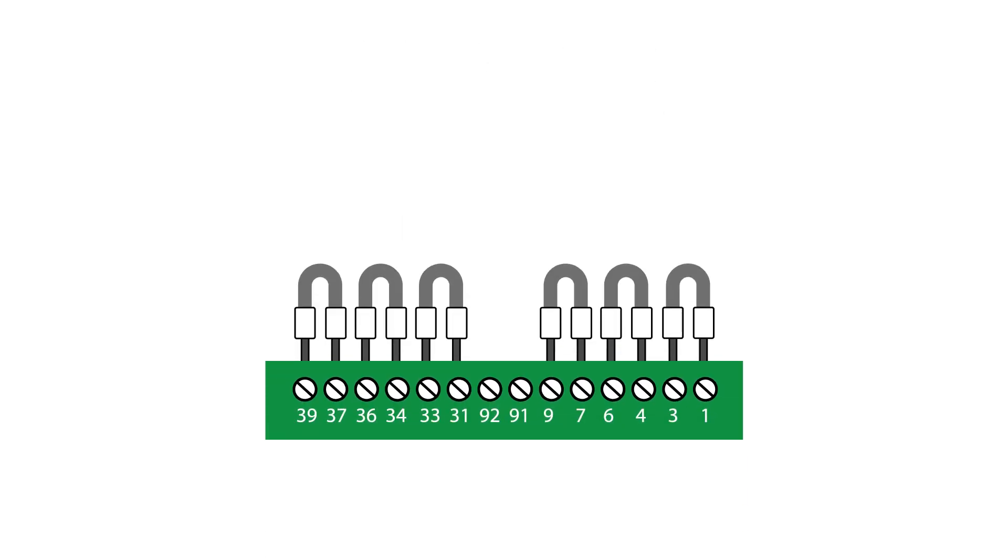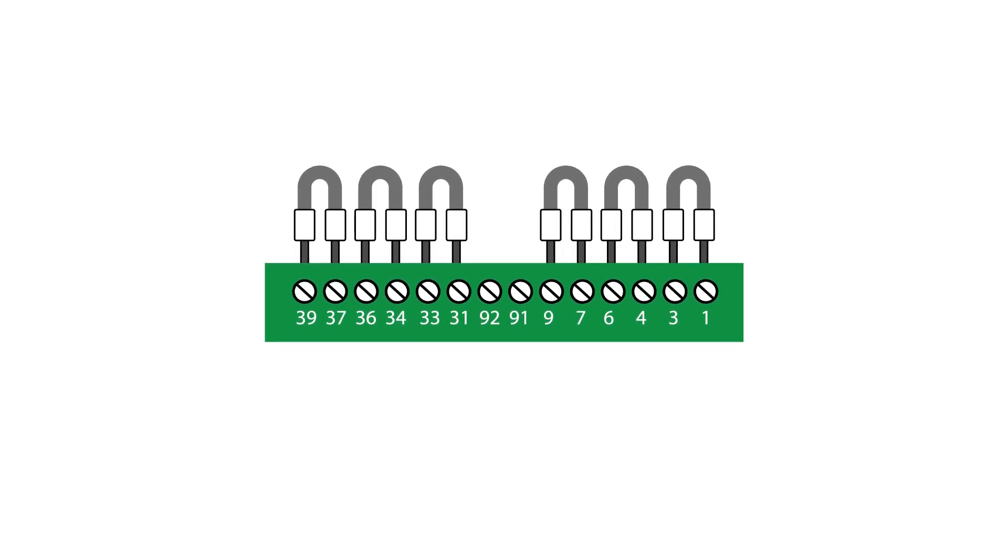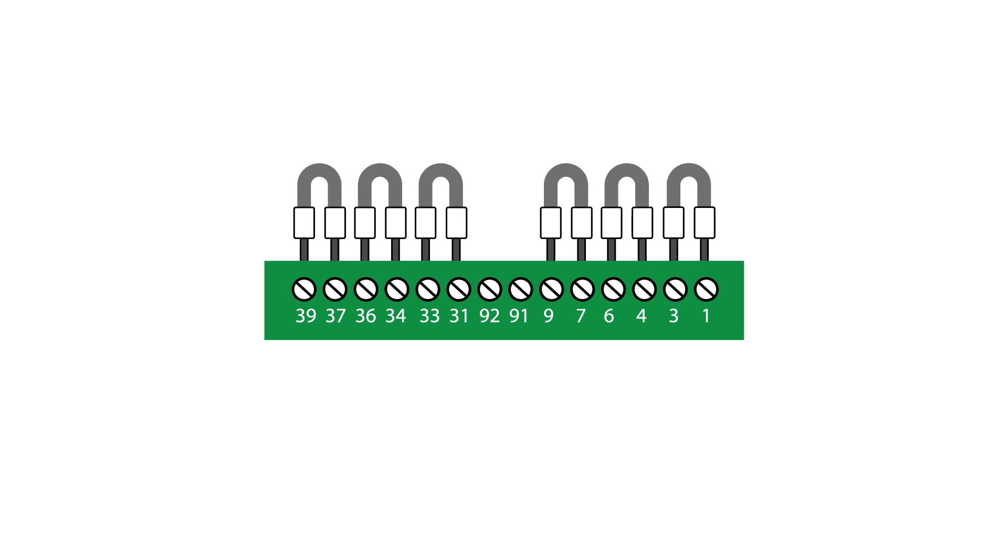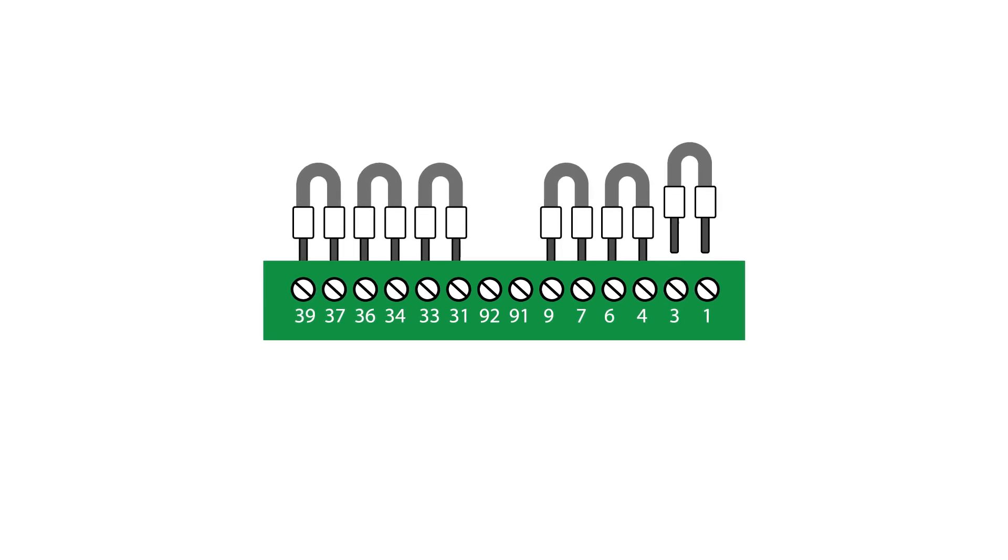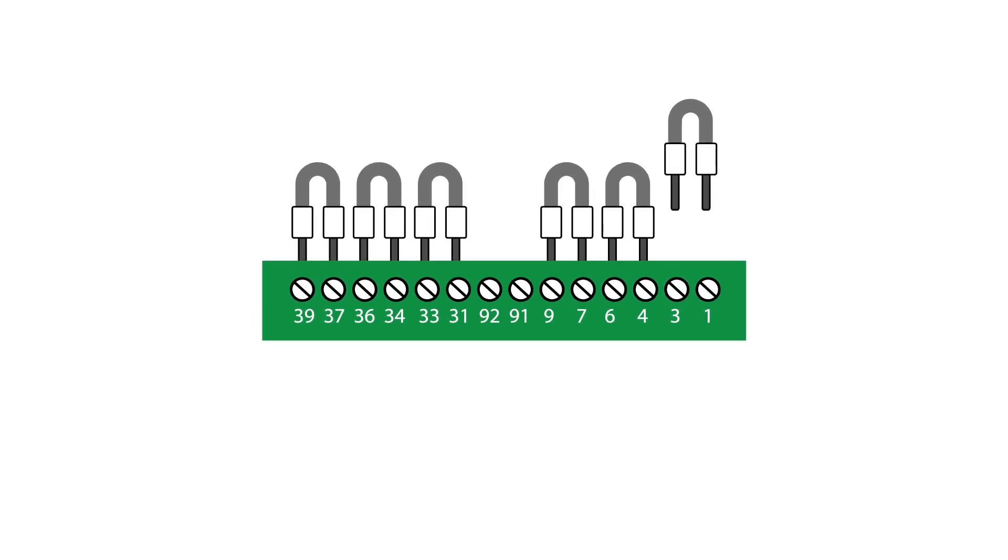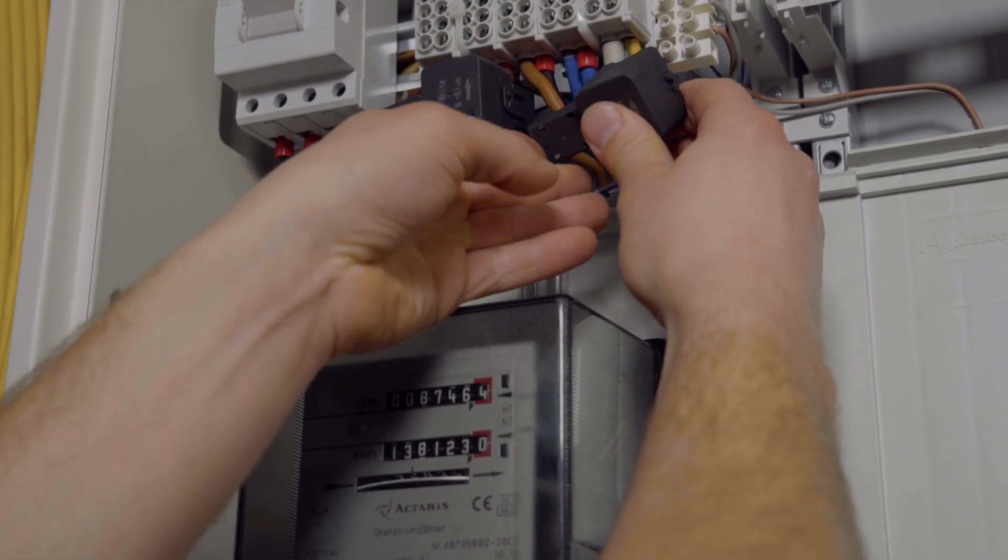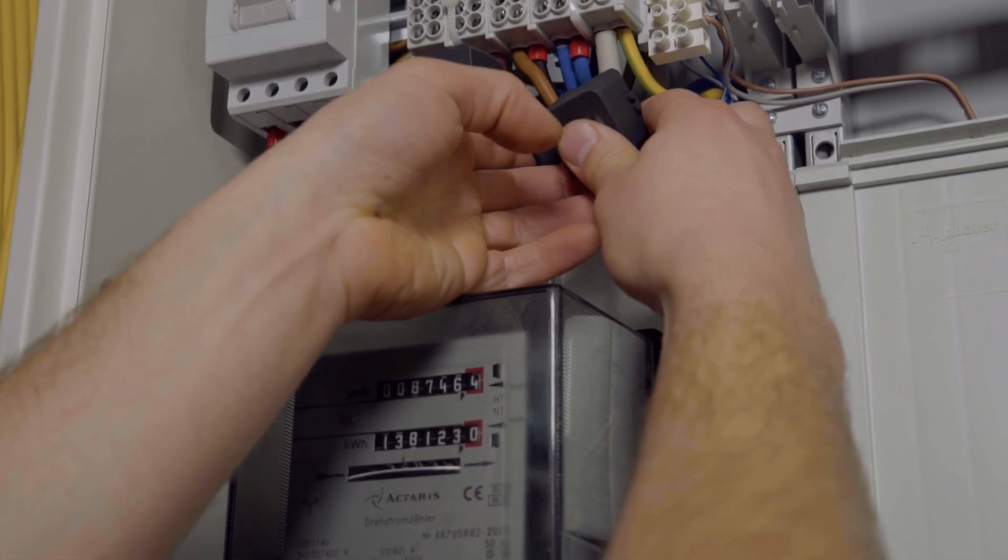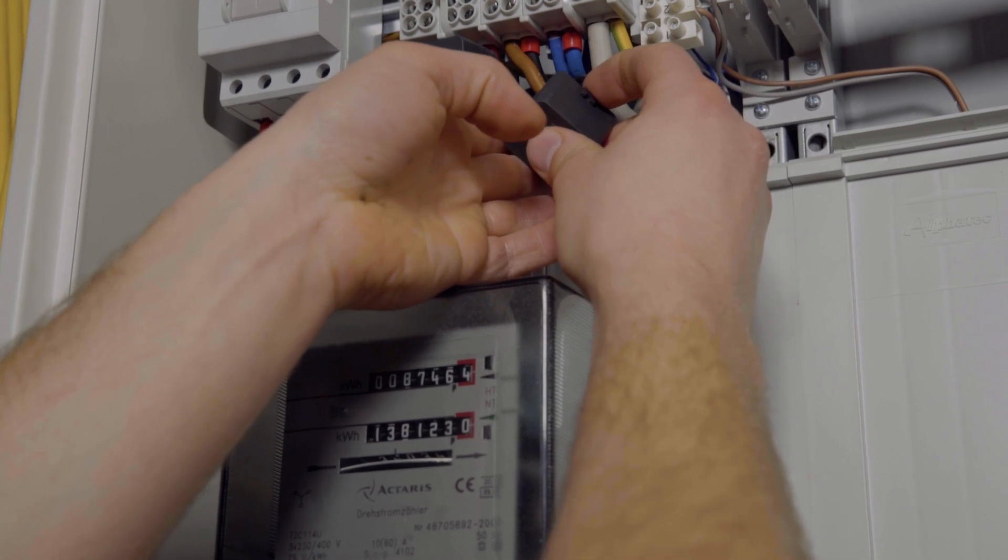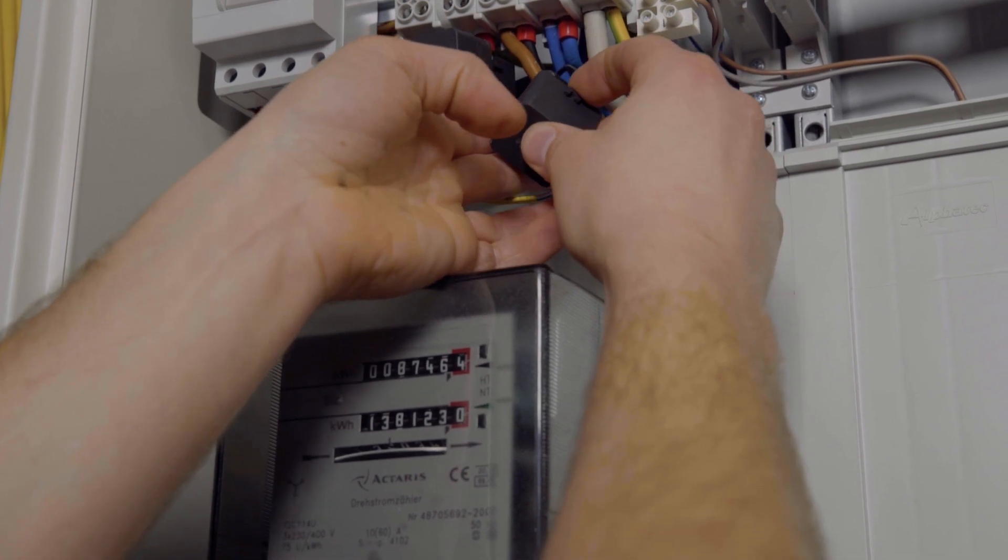If the meter comes with pre-installed shorting wires, please remove only the ones where you need to install the CTs and leave the other shorting wires plugged in. Then install the CT to the AC cable where the current must be measured.